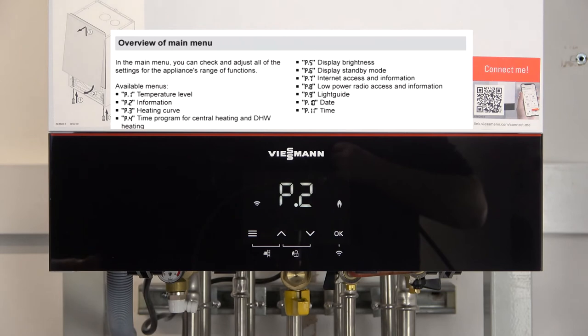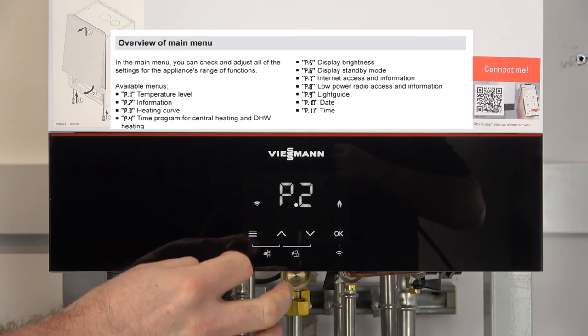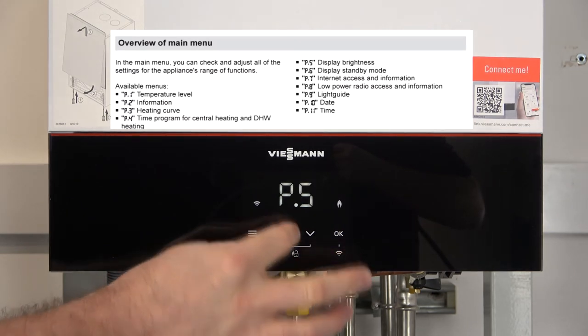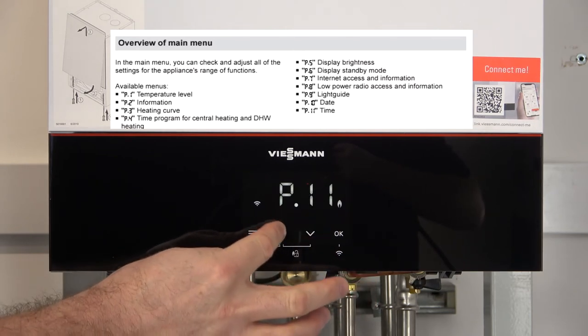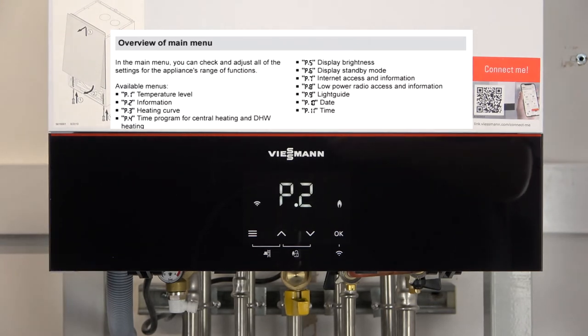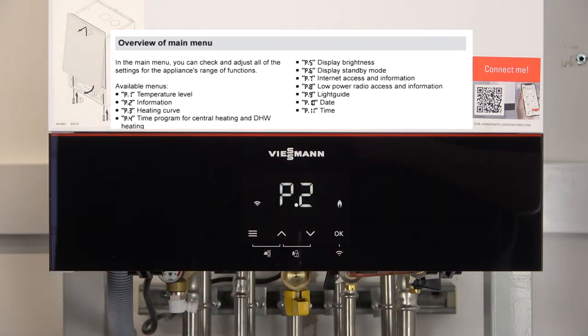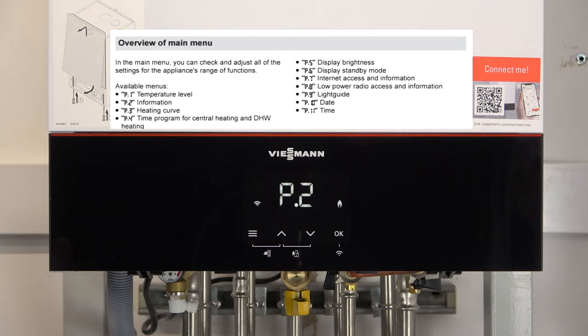For this example, when we went into the P-Menus, P-2 appeared straight away meaning that P-1 is not available. To toggle through the P's we just press the up or down arrows, and we can see there's no P-1. P-1 is actually our temperature level, so if we were using the internal timer inside the display to control the boiler, P-1 would then become active. In this scenario, I've actually got C-7 set to number 13, which is external demand, so P-1 will not become available.